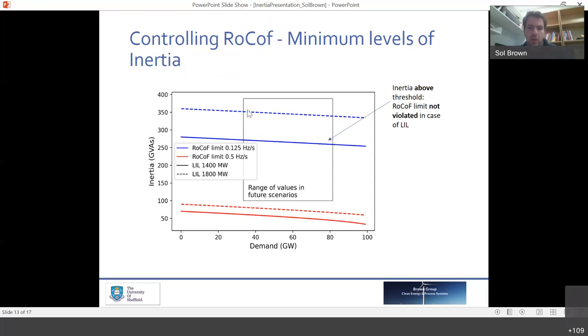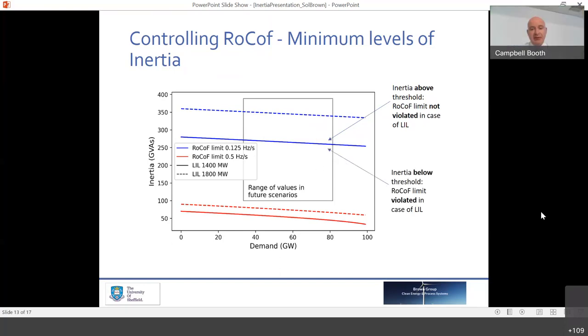So anything above this curve means that your RoCoF is not going to be violated in the case of the largest infeed loss. And if we're below here, then we violate. So you can see that with the change in the definition of the RoCoF, we're allowing ourselves to drop quite significantly in the amount of inertia that's required, but we're still above 50 GVAs.